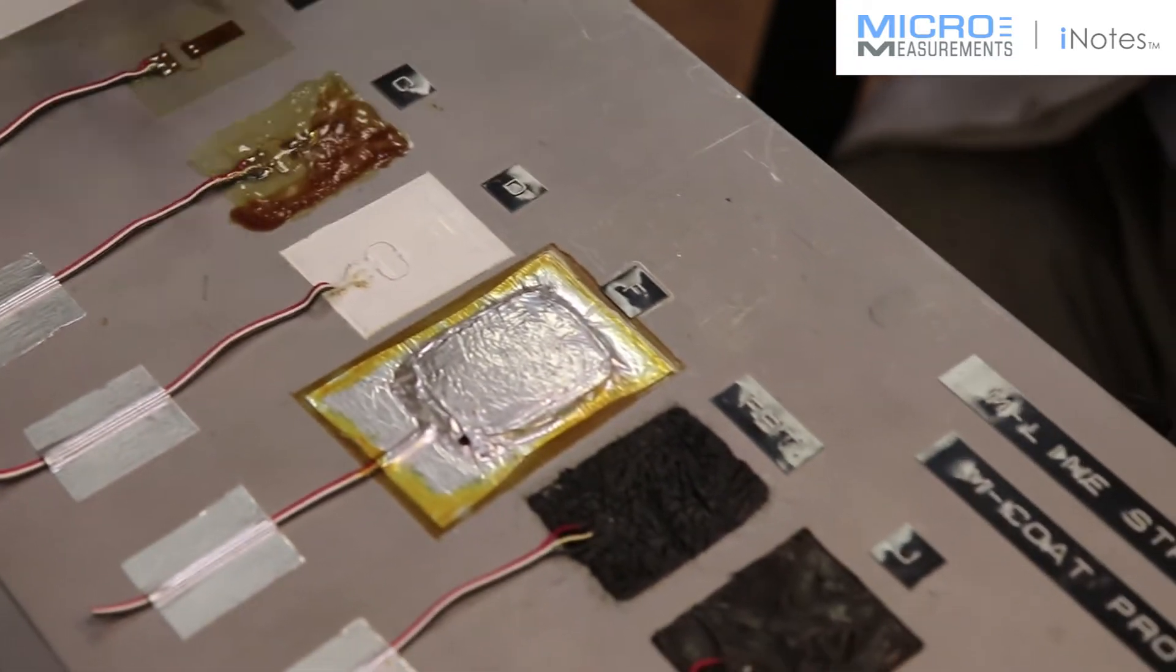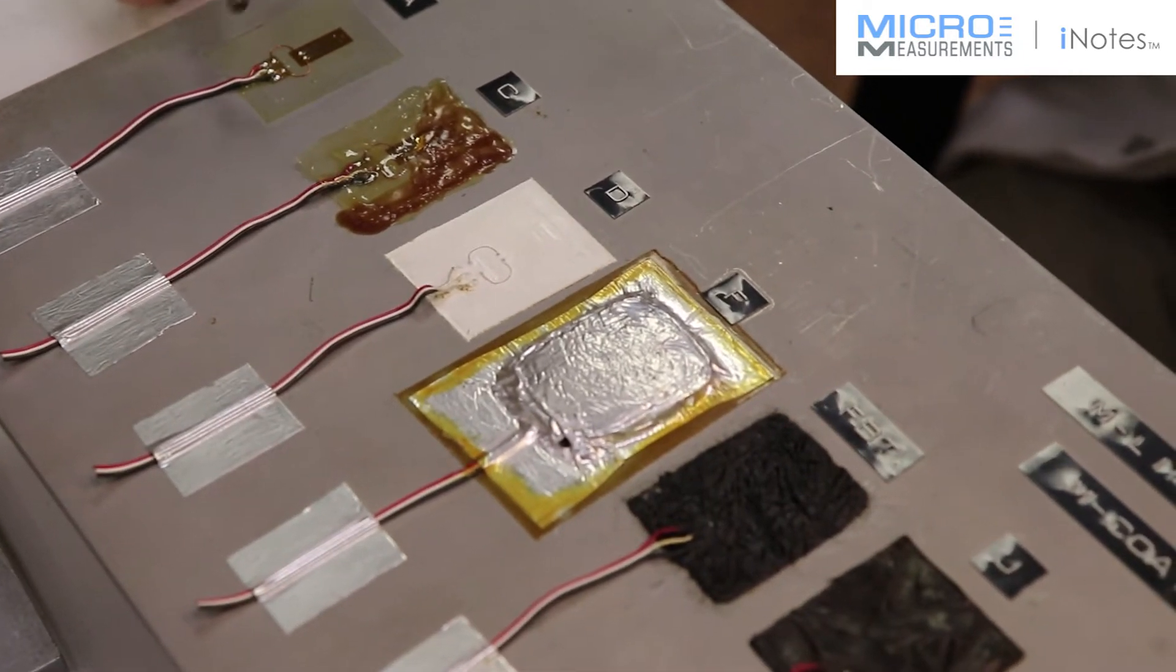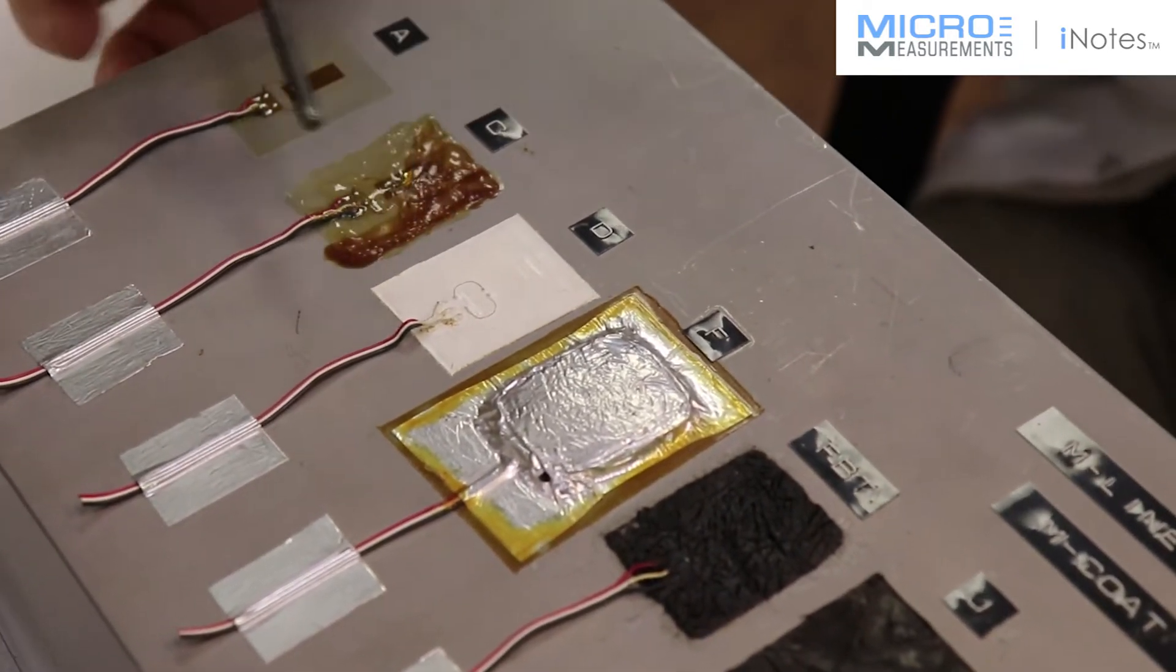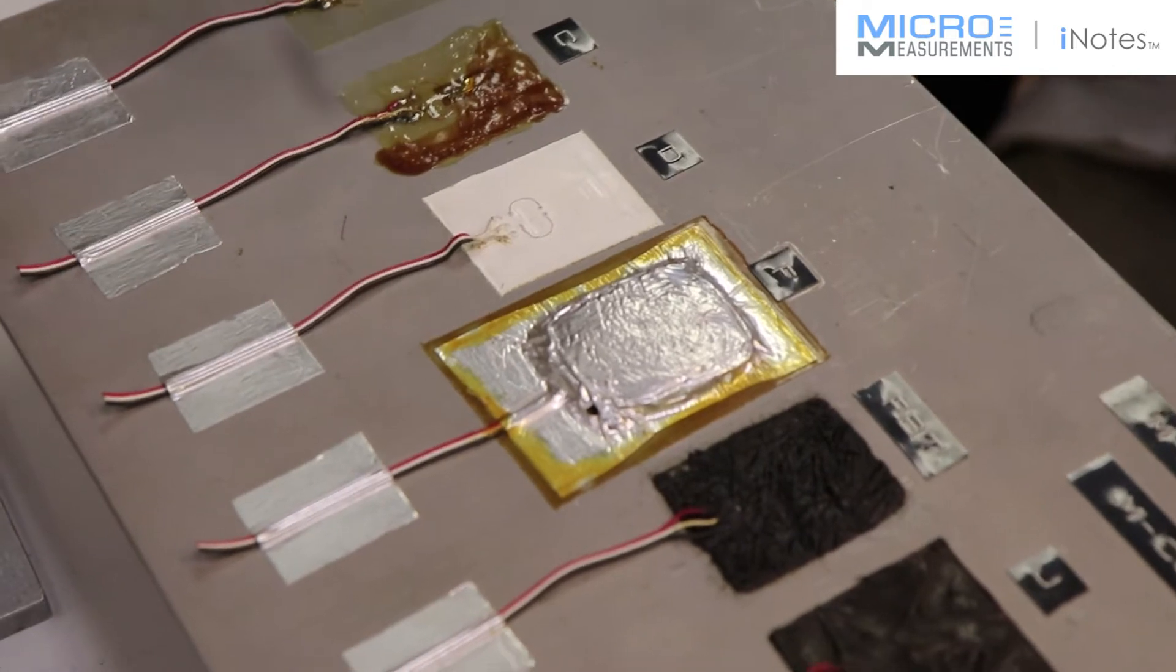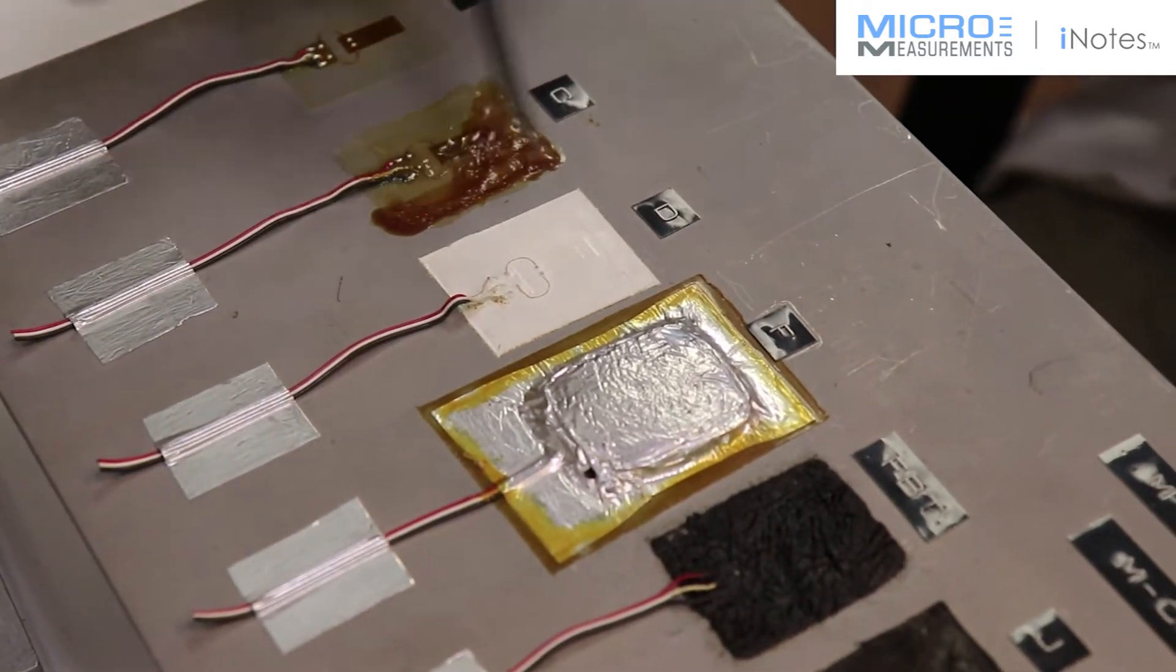M-Coat D, it's an acrylic material, typically used for laboratory conditions and or short term exposure outside. I like it because it's white and when you've finished a strain gauge installation you know for sure if it's still brown, it's not finished. If it's white, you're done.